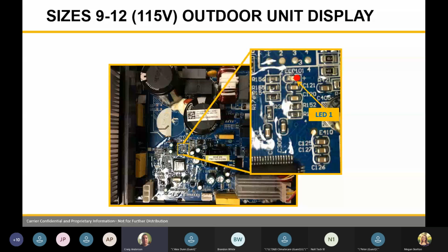So on the 9s and 12s, 115 volt, these have LED lights on the board. So when you're looking at it, it's like a furnace, you're going to be counting the flash codes. Look at the panel on the unit, it's going to tell us what those flash codes mean. Or if you have the manual, it's going to tell us in the manual what we're looking at. So these flash codes are giving us an idea where we need to look next for our servicing.